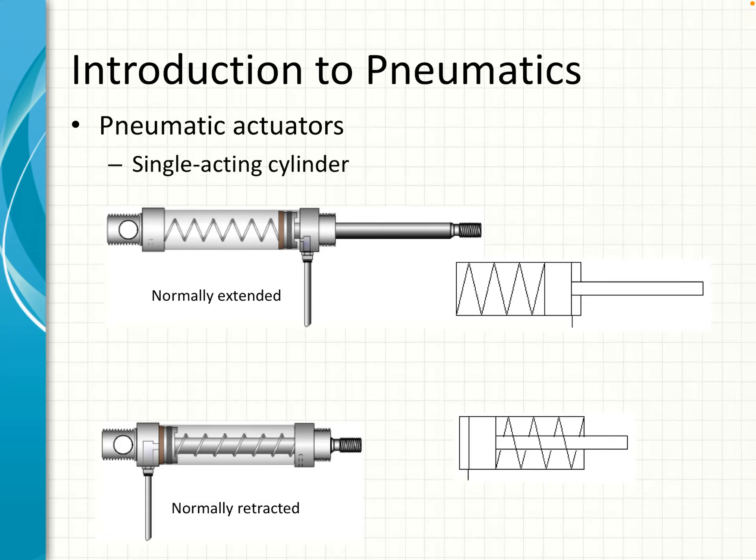In this video we're going to talk about pneumatic cylinders and valves. Here on this first slide we have a single acting cylinder, which is either normally extended or normally retracted, and we only have one input for the pneumatic pipe. For the bottom one, it's normally retracted — that's the more common design. If we put an air supply onto the pipe it will extend the cylinder; if we take it off, the spring will bring it back.